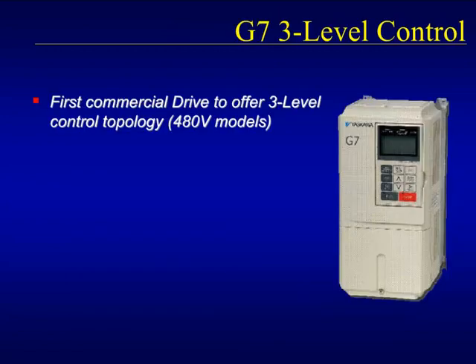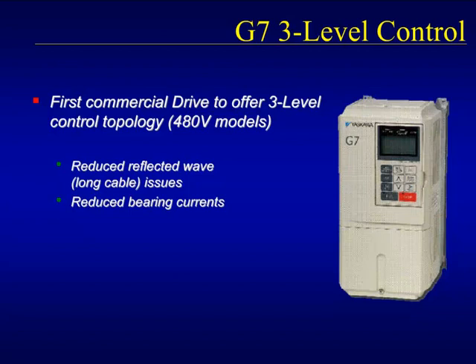The G7 drive is the first commercially available drive to offer 3-level control on its 480-volt models. On the next few slides, we will cover the benefits of using 3-level control, such as reduction of motor surge voltages due to long motor cable lengths, reduction of motor bearing currents to levels that will not destroy the bearings, reduction of leakage currents synonymous with the common mode noise, and reduction in the effective audible noise of a motor caused by PWM switching.